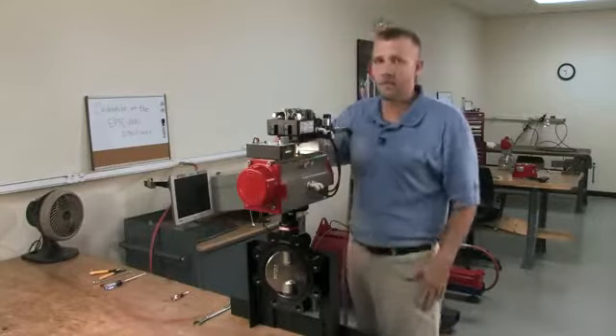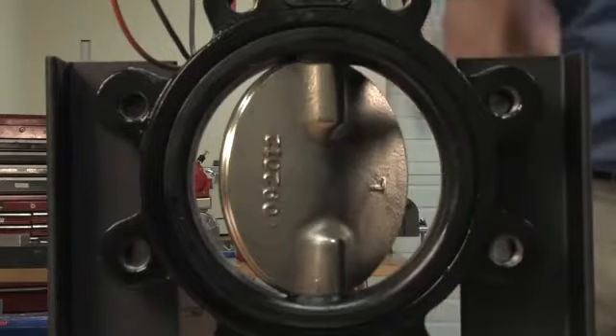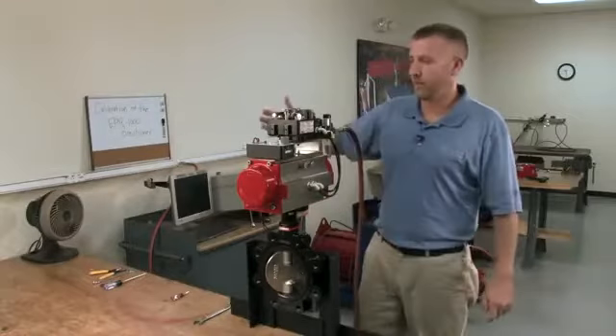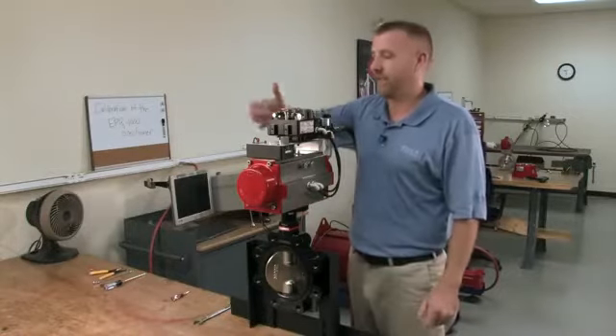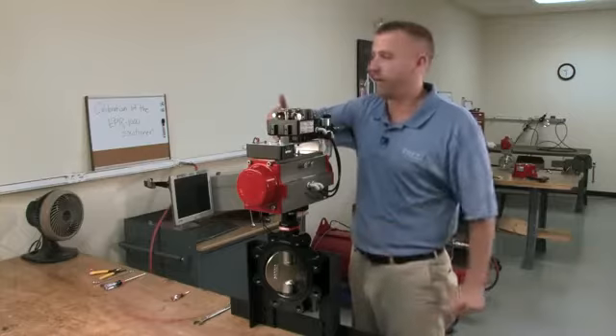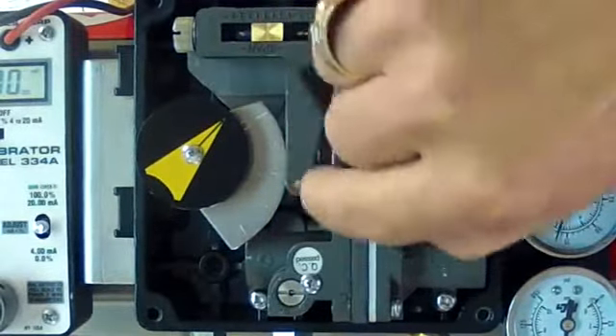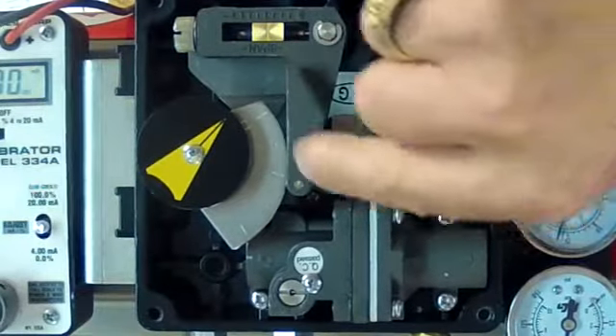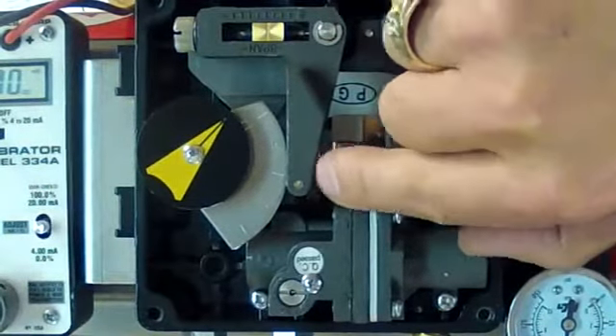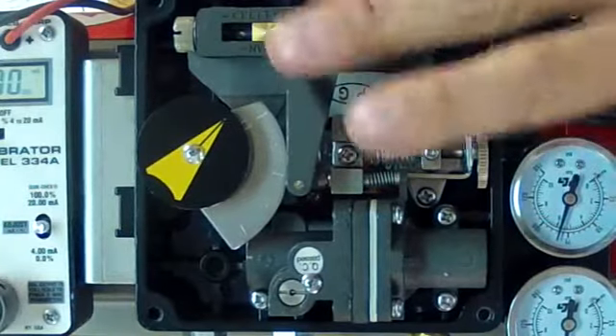Now what you're looking for in your mid position is a nice 45-degree angle on our disc. Or if the package is in line and you cannot see your disc or your ball in your valve, a reference point on our travel cam is the mid line here. Should be somewhere in line with the bearing. It doesn't have to be perfect, but that's just a reference point.